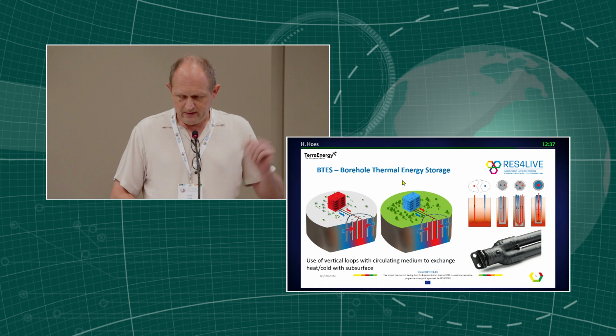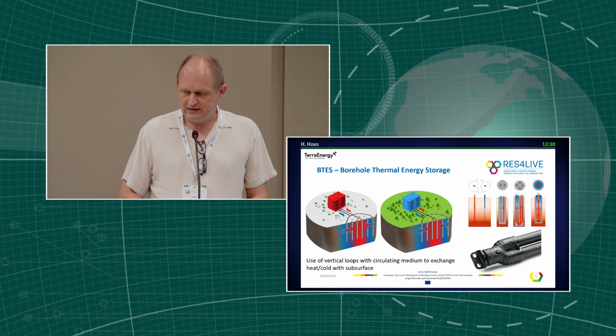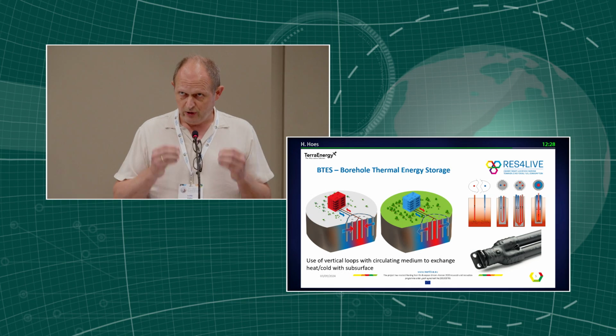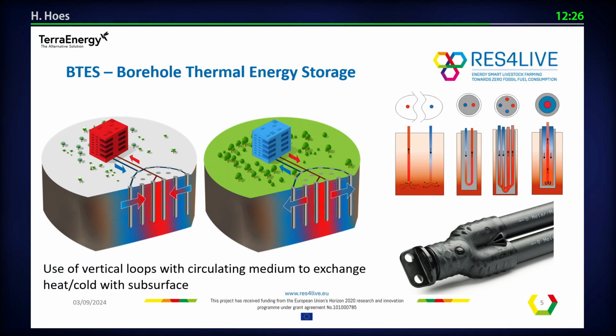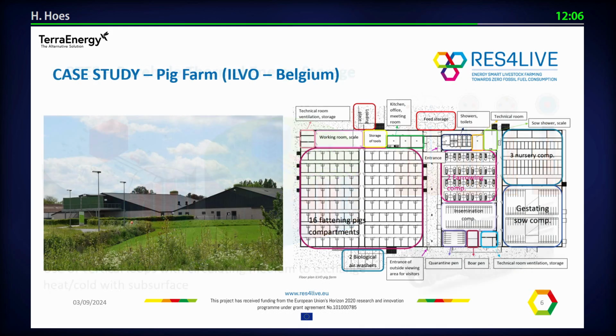The other system, I want to be short here, that's already explained by Stefano. It's a borehole thermal energy system where you use vertical loops that you put in the underground and you exchange energy while circulating this fluid, typically a water glycol mixture. You can do it several ways.